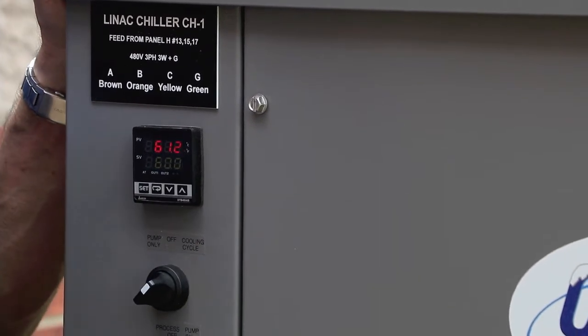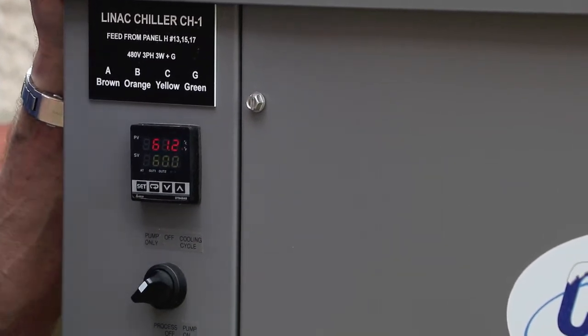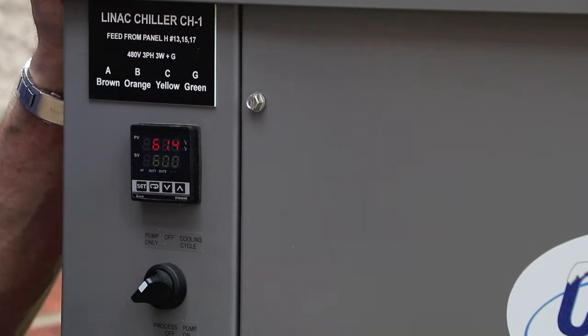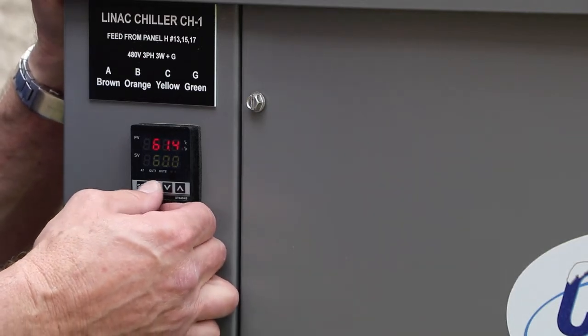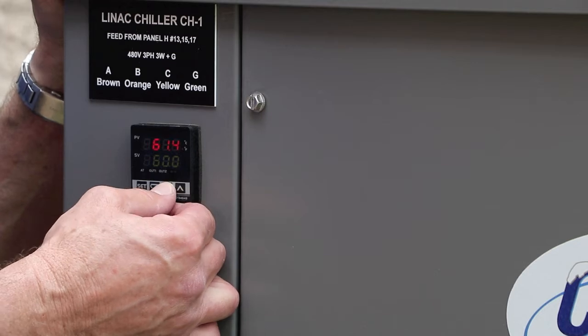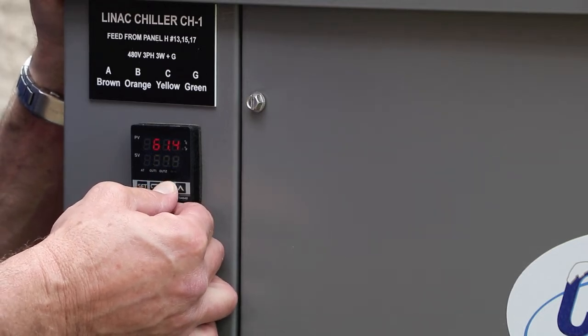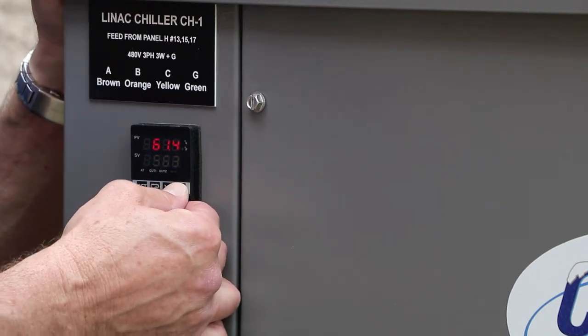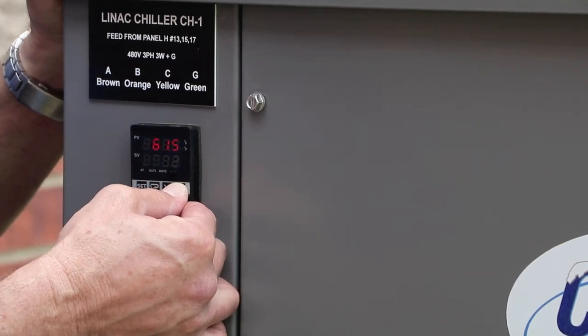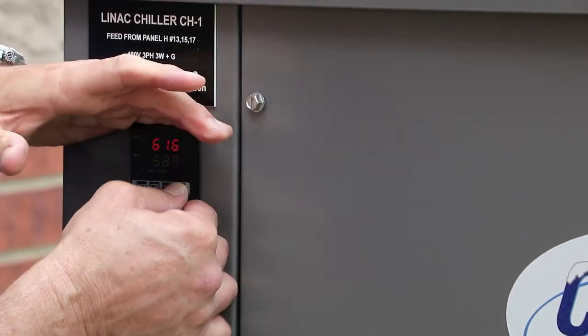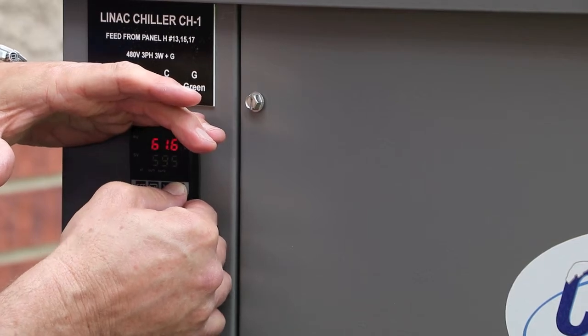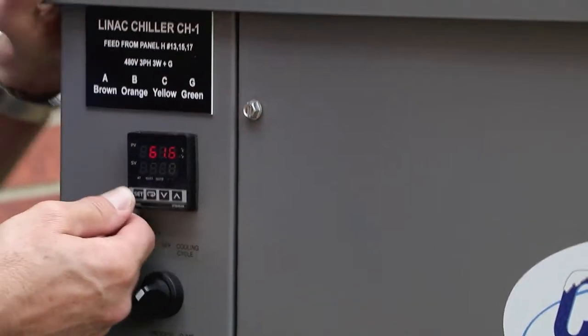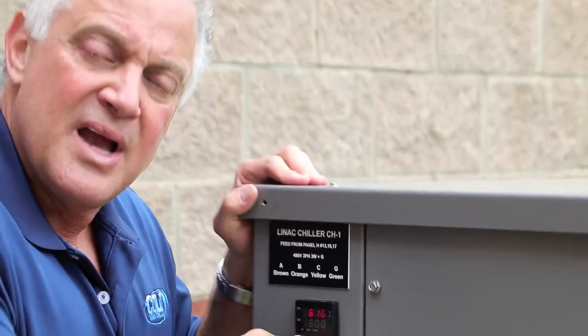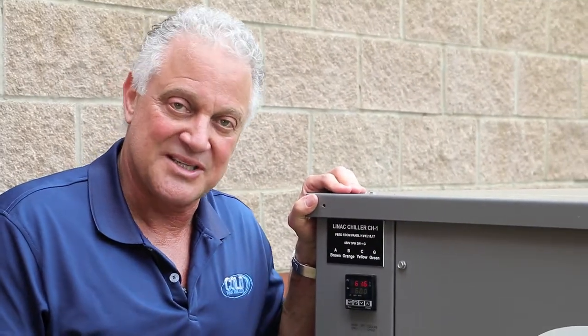This application requires a 60-degree set point. It allows for enough cooling for the linear accelerator while being warm enough to not develop any condensation within the control panel. To adjust the set point, we come to the scrolling keys over here to the right and scroll up or down to our desired point. Once we reach where we want to be, and this one will be 60 degrees, we come up to 60. We press the set button over here, and now our chiller set point is set to 60 degrees.